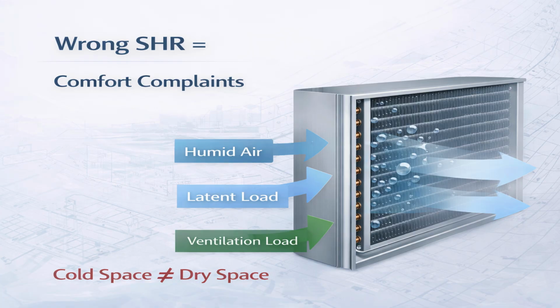Sensible heat ratio, or SHR, tells us how a cooling system divides its capacity between temperature reduction and moisture removal. In simple terms, it explains how much of the unit's cooling effort is used to cool the air and how much is used to remove humidity. Every space has its own requirement. Some spaces are dominated by sensible heat, others carry a high latent load due to occupancy, fresh air, or local climate. If the selected unit SHR does not match what the space actually needs, problems are inevitable. The room may reach the set temperature, but it will still feel uncomfortable, sticky, or heavy. And no matter how much tonnage we add, the discomfort will not go away, because the issue is not capacity, it's how the capacity is being used.